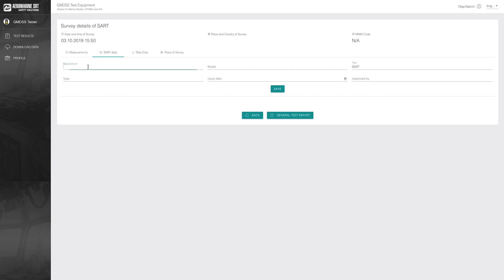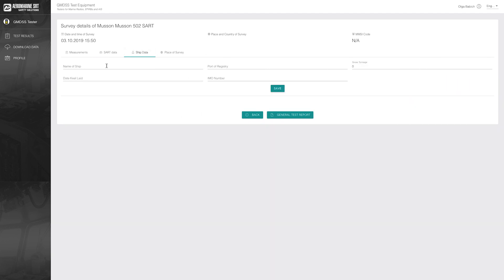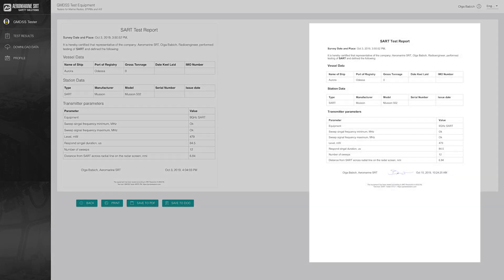Input the SART data and vessel details here. Now just generate the test report by simply pressing this button. This test report can be saved or printed immediately. Here is the ready test report. We can sign and issue it to the captain of the vessel.